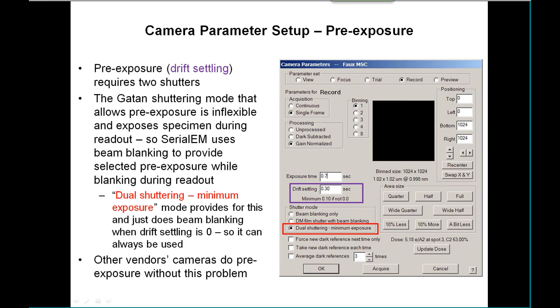Historically, the GATAN cameras have a shuttering mode that does allow pre-exposure, but it's very inflexible and exposes the specimen during the camera readout, which can be a number of seconds.